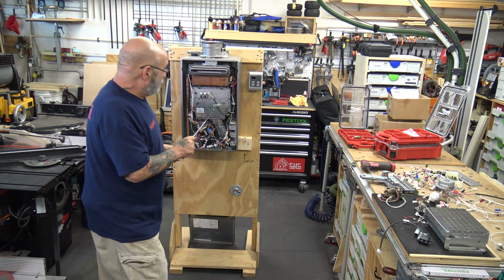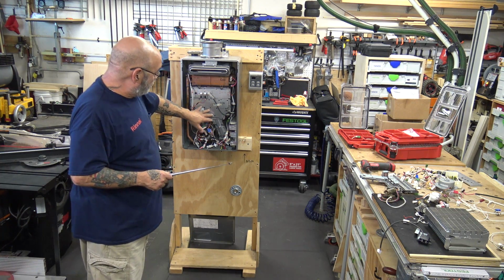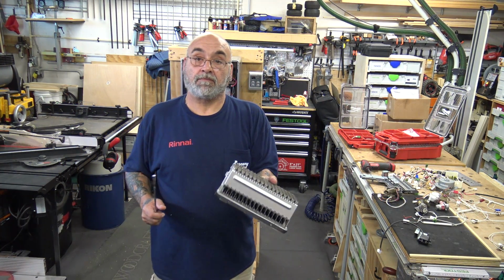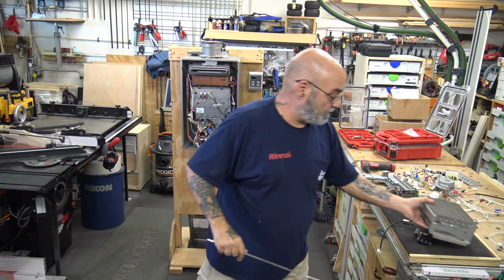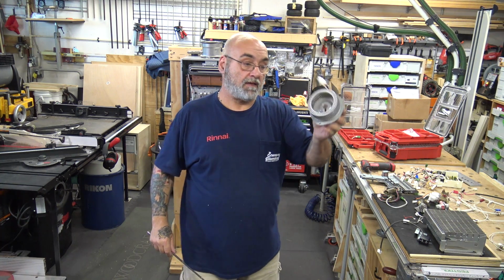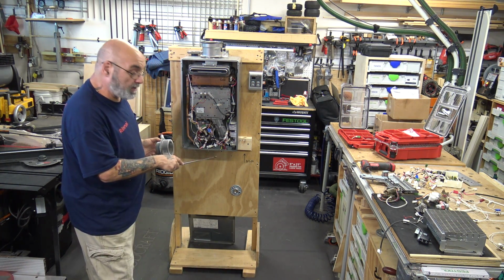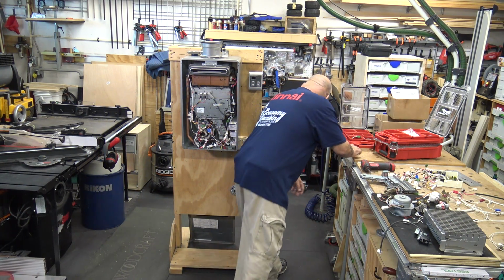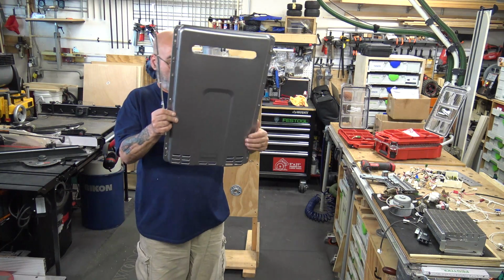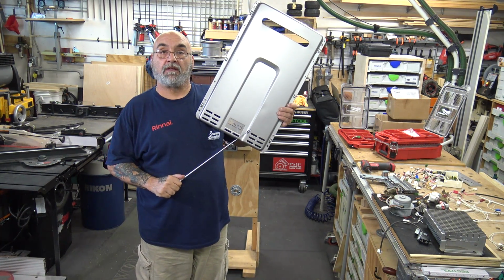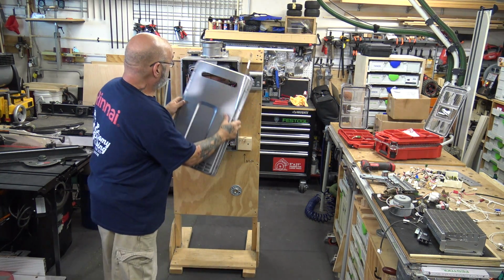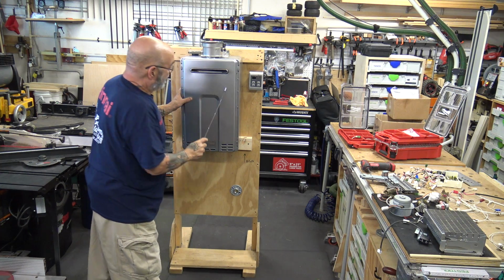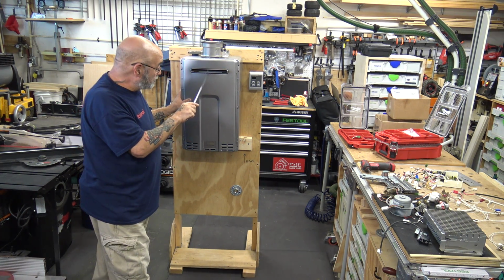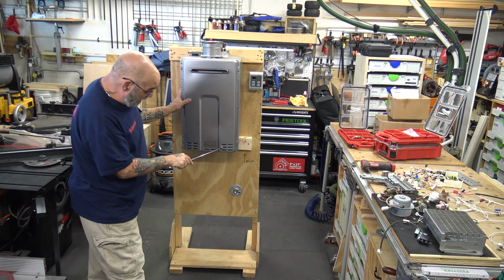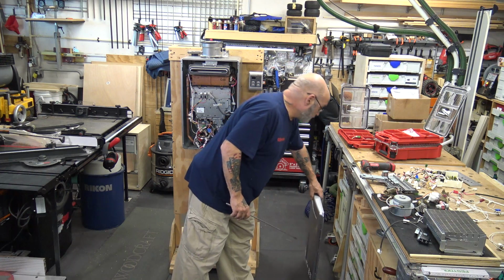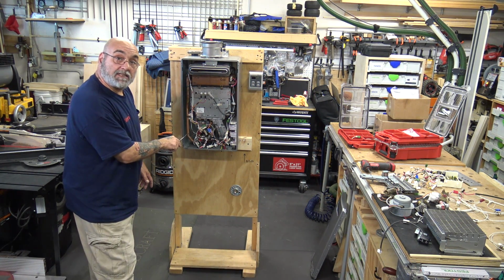So now, you have one sink on. You're on low fire. The burner is heating. The fan right here is drawing in fresh air on an external unit. It's drawn in from right here, and it exhausts through there. So when the cover is on, that's why that rubber seal right here is very important, because you don't want to start drawing air through here. You want to draw air through here because there is a pickup back here that's picking up the fresh air.